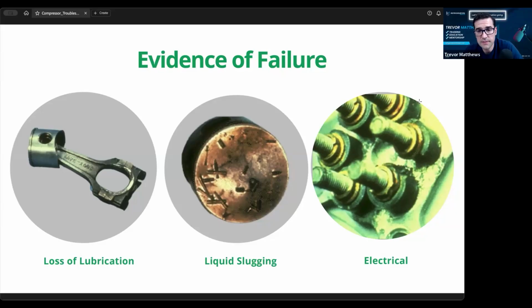Yeah. And not really lose any gas. I have so many people talk about, well, I have to remove all the refrigerant out of the system. Well, why? Just close your suction and discharge if they're holding, and on your oil return there on the rack system, you'll have an oil return. And so close those valves and just change the compressor out. You don't lose it. You really don't lose much refrigerant.